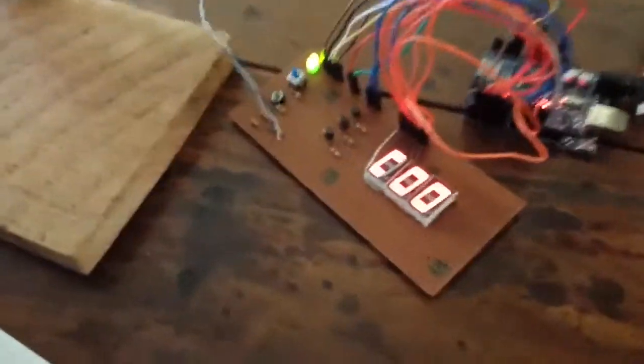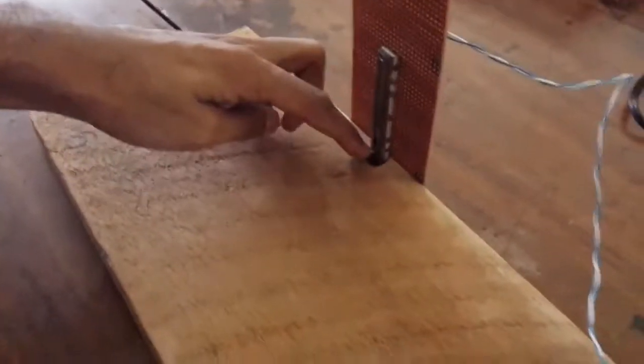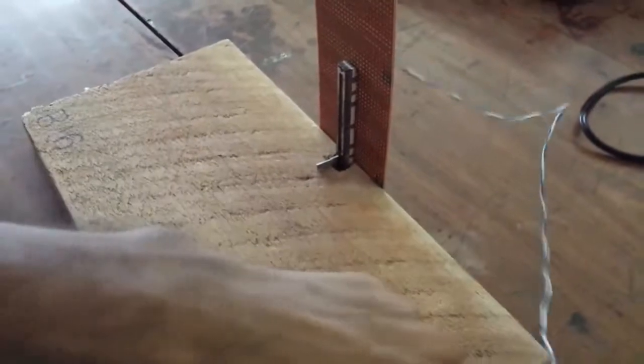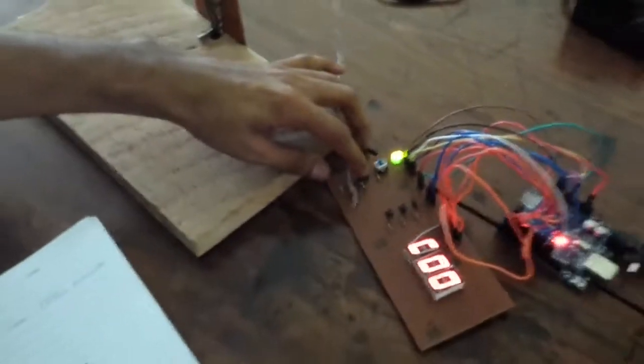The device needs to be calibrated first. The calibration is done with no papers on the tray first, and then with 10 papers on the tray.